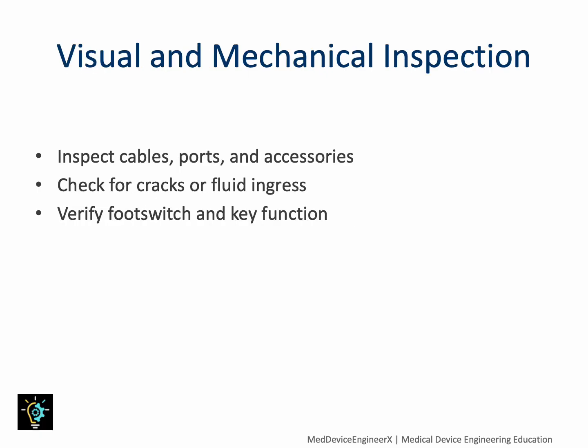Start with a detailed inspection. Examine every cable and port for wear or discoloration. Look for cracks, corrosion, or liquid residue that could signal fluid intrusion. Test the activation switch and foot switch for smooth, responsive operation. Visual checks may seem simple, but they often reveal early signs of wear or overheating. Document all findings before moving on to electrical testing. This baseline helps track long-term reliability.